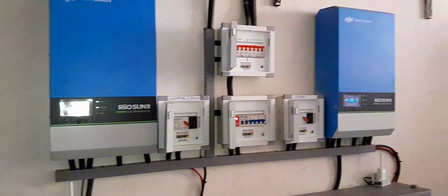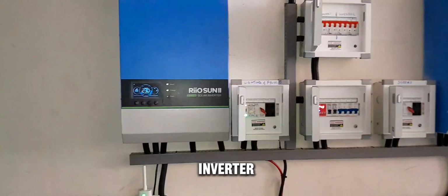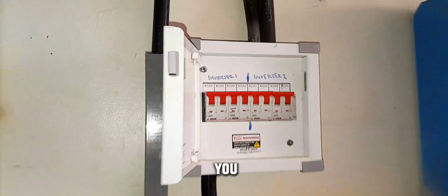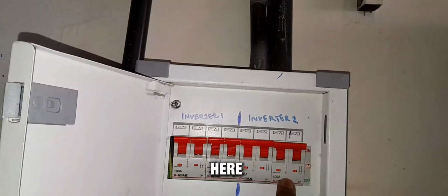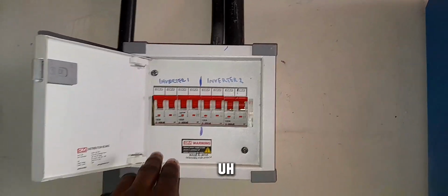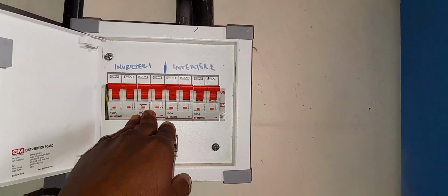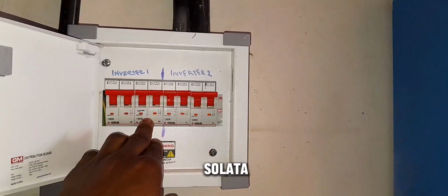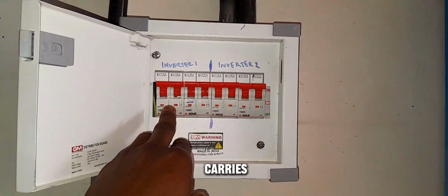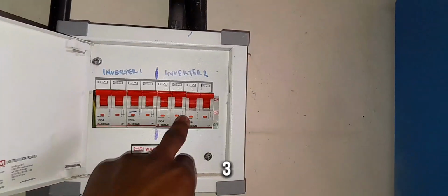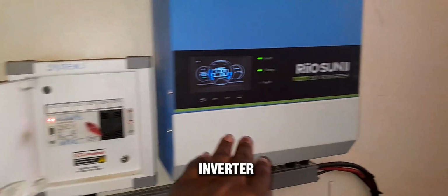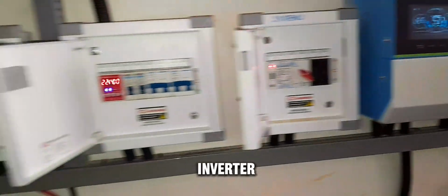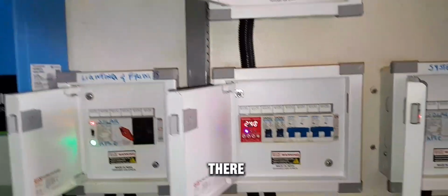So this system has 20 solar panels, and like I said before, each inverter has 2 MPPTs. That is why you see we have 4 isolators here. Each isolator carries 5 solar panels. So 1, 2, 3, 4, those are 20 solar panels, and then 10 come into this inverter and 10 come to this other inverter.